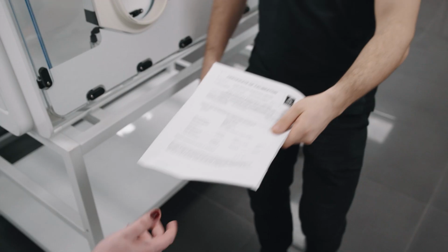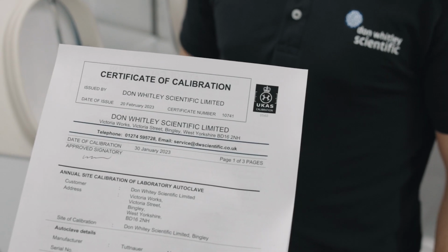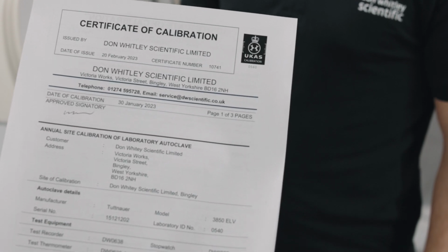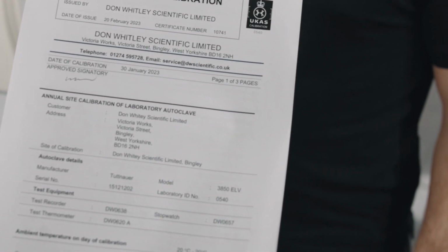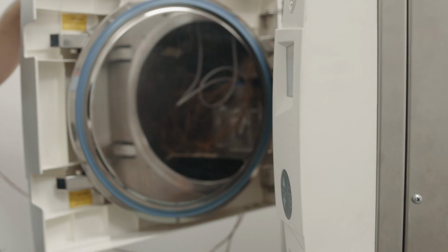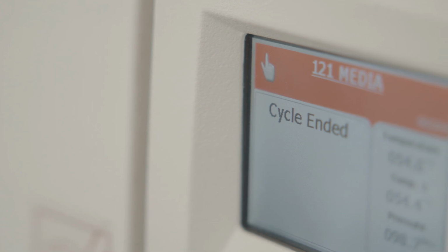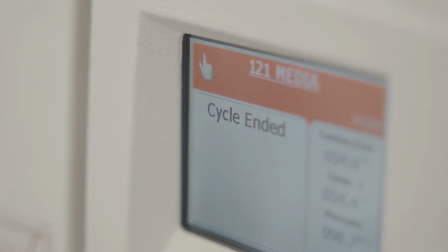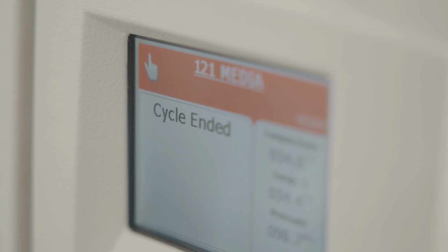In general, once a validation has been carried out, and providing that no changes have been made to the load or the settings, calibration of that cycle going forward is sufficient. However, it is always worth reviewing any validation periodically to ensure the validated cycle still meets your requirements.